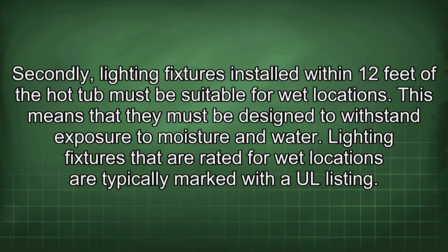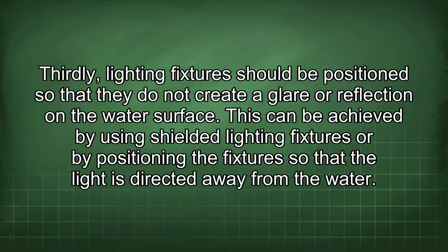Secondly, lighting fixtures installed within 12 feet of the hot tub must be suitable for wet locations. This means that they must be designed to withstand exposure to moisture and water. Lighting fixtures that are rated for wet locations are typically marked with a UL listing. Thirdly, lighting fixtures should be positioned so that they do not create glare or reflection on the water surface.